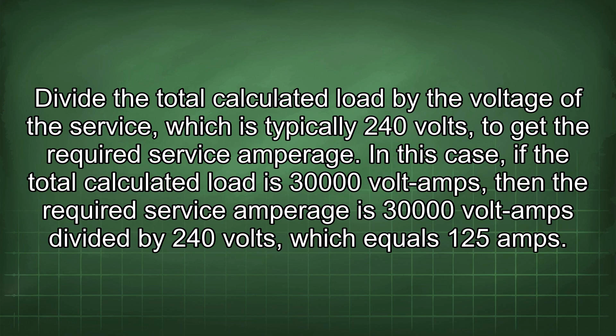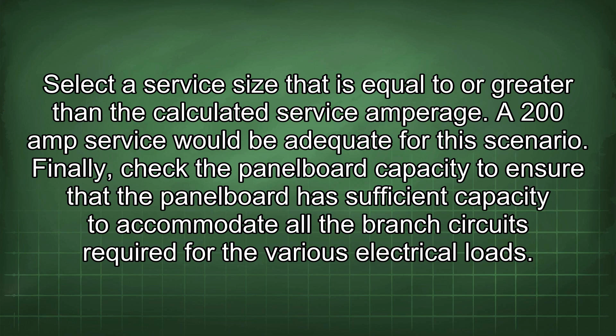Select a service size that is equal to or greater than the calculated service amperage. A 200 amp service would be adequate for this scenario. Finally, check the panel board capacity to ensure that the panel board has sufficient capacity to accommodate all the branch circuits required for the various electrical loads.